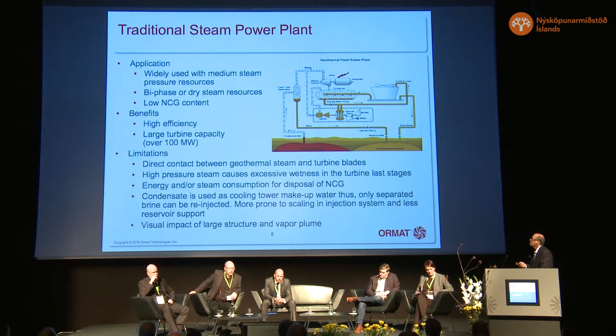The application is mainly used in medium pressure steam. Right now, most of the technology is for 8 bars inlet, mainly due to the wetness at the last stages. It can use either biphase steam and brine, when the brine flashes to the second flash, or dry steam, and it's mainly used where NCG content is low. The benefits are, of course, the high efficiency of the steam turbine and the large capacity. I think in New Zealand there are turbines of more than 200 megawatts.